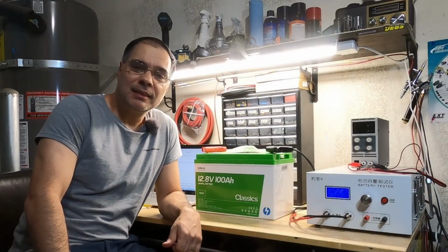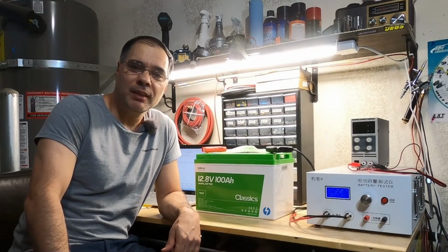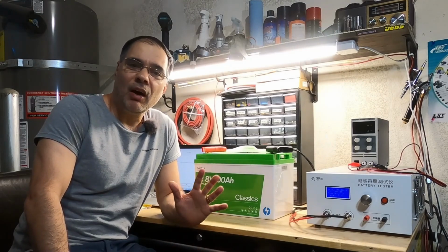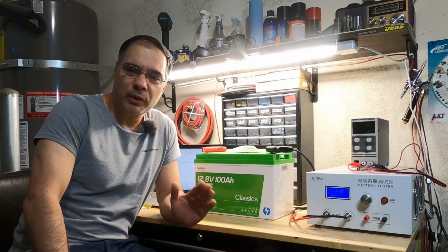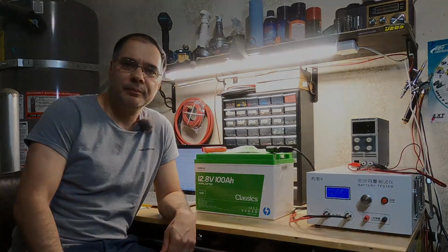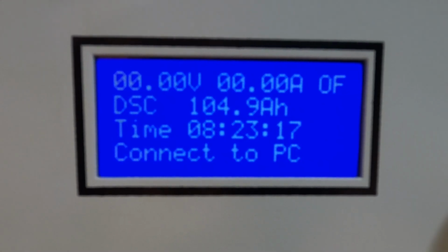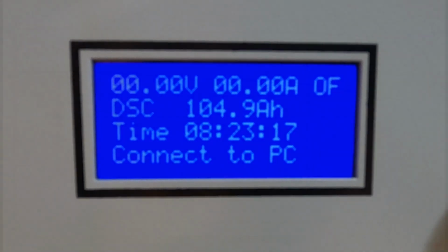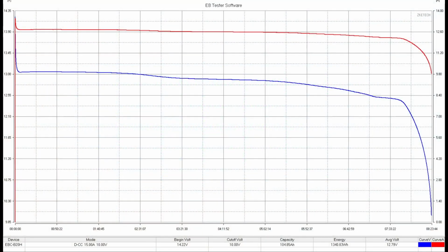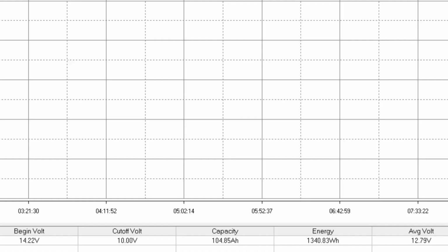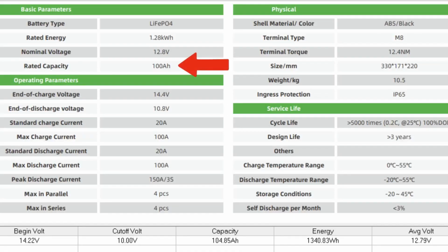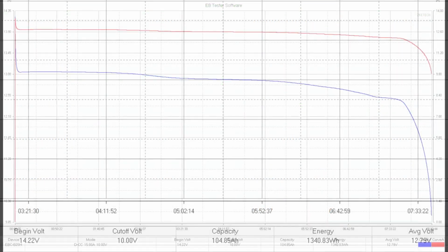Okay, the capacity test is done. It's been 8 hours and 23 minutes. We discharged the battery all the way down to 10 volts, and that's where we cut off. Let's take a look. 105 amp hours. So that's pretty good. We have a very nice discharge curve. The rated capacity is 100 amp hours or 1.28 kilowatt hours, compared to our test results of almost 105 amp hours at 1.34 kilowatt hours.